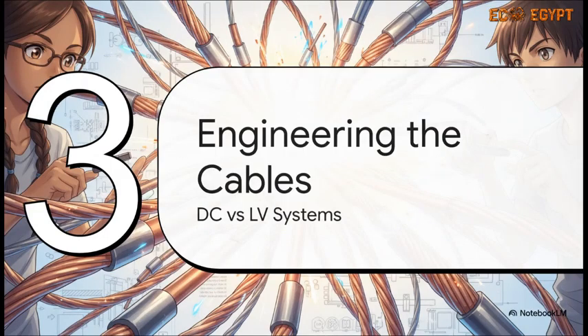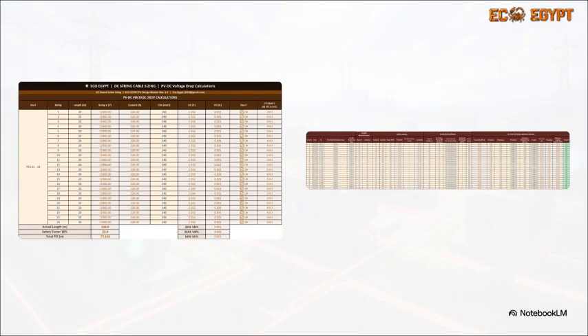Which brings us to section 3, engineering the cables. With those massive core components locked in, engineering the physical cables is literally about bridging two completely different electrical worlds. We're taking a 1500-volt direct current battery system and linking it to a 33 kilovolt AC coupled connection. And the engineering math required for each side? Totally different. On the DC side, engineers are obsessing over string lengths and how much current the cables can handle in the sweltering heat. But flip over to the low-voltage alternating current side, and suddenly it's all about how deep the cable is buried, grouping factors, and the thermal resistance of the dirt.